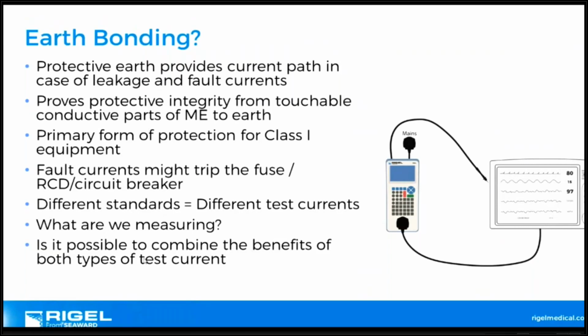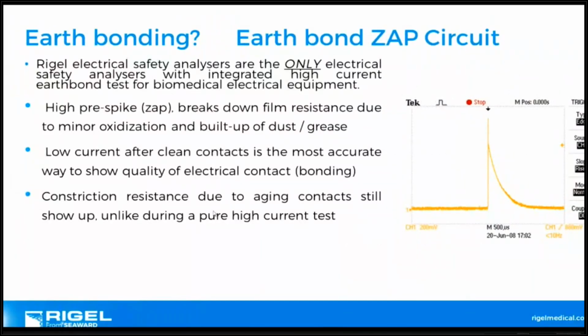Is it possible to combine the benefits of the different currents? Well, yes, it is. We have the Rigel electrical safety analyzer. It gives you a spike of current. It's a low current because that's the nature of safely measuring low resistance values to make sure that you have a real solid mechanical connection. When you've been screwing the device back together, if you're using a low current, you can pretty much identify if you have a really poor mechanical joint. And that's why we use low current.